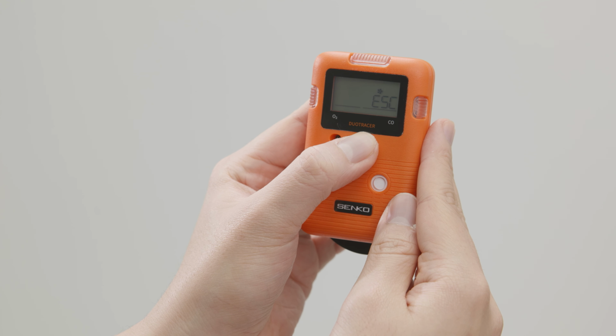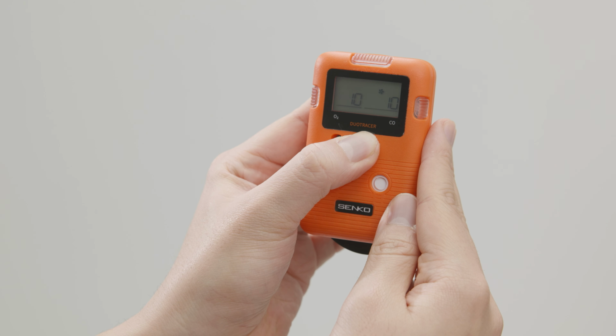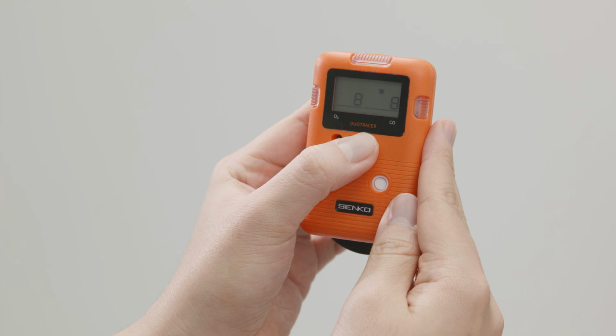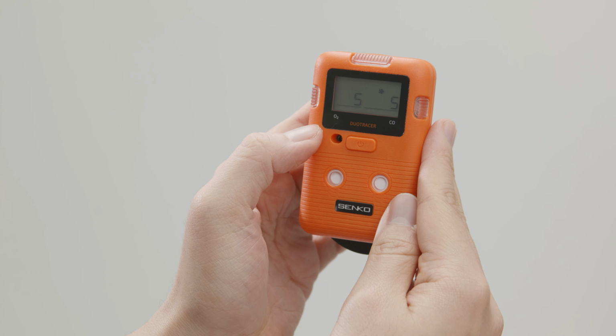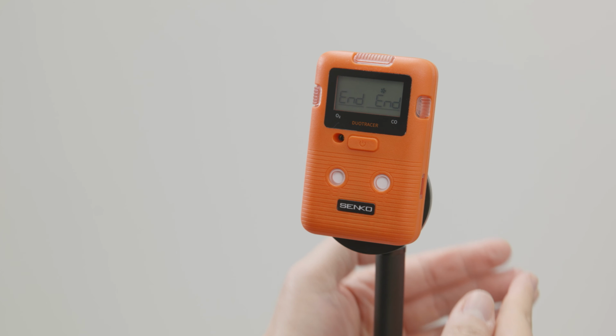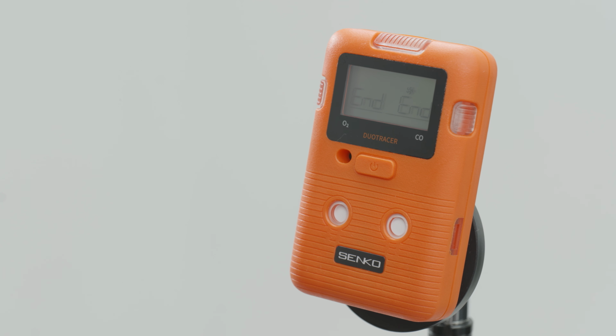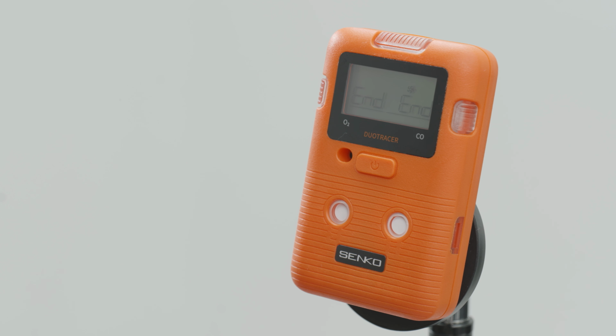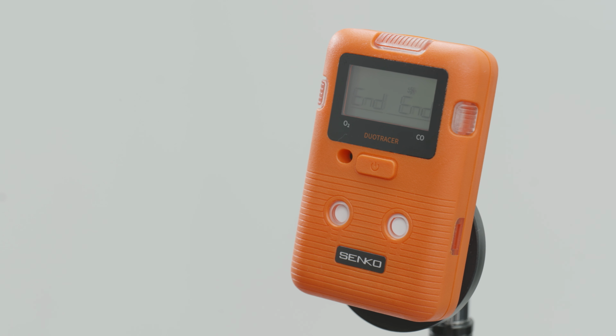Once you've selected the gas channel you want to calibrate, press and hold the button again for about 10 seconds to start the zero calibration process. Now, there's one important thing to keep in mind. For accurate and safe results, zero calibration must always be performed in a clean air environment. When the calibration is completed successfully, you'll see an end icon on the LCD screen. If something goes wrong and calibration fails, an FA message will be displayed instead.